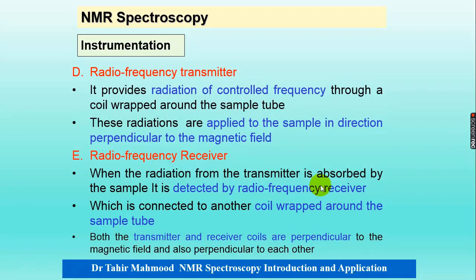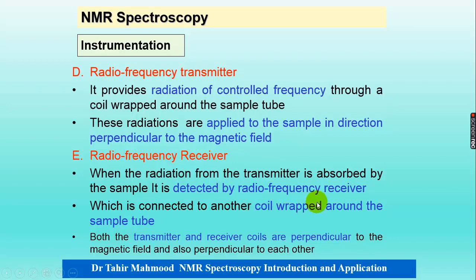The radio frequency transmitter provides radiation of controlled frequency through a coil wrapped around the sample tube, and these radiations are applied to the sample perpendicular to the magnetic field. Similarly, the radio frequency receiver detects the radiation absorbed from the transmitter via another coil wrapped around the sample tube. Both coils are perpendicular to each other and also perpendicular to the magnetic field.